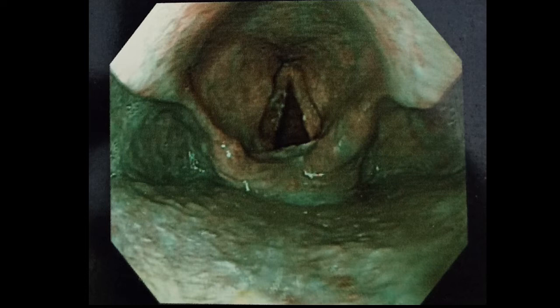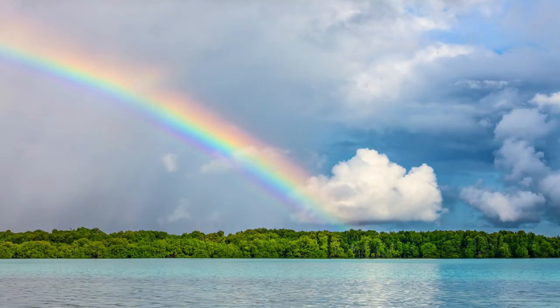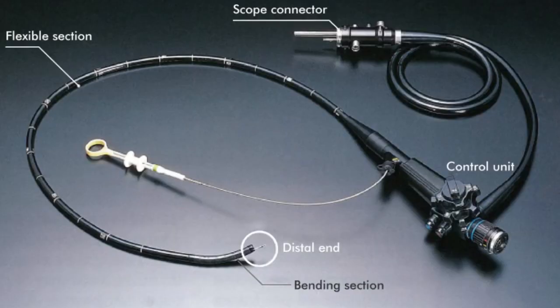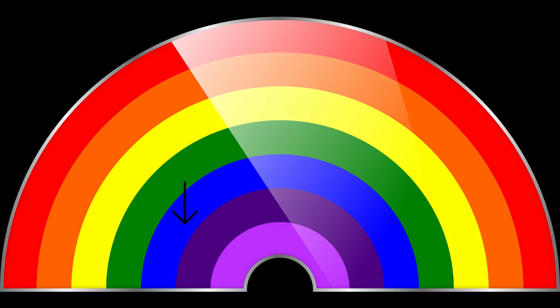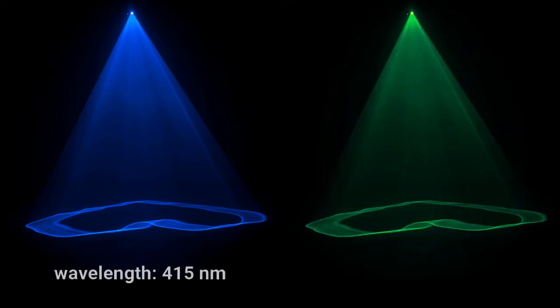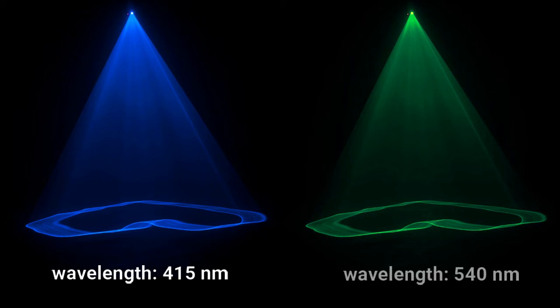Normal light has seven colors in it. In narrow band imaging, with the help of a switch in the endoscope, a special filter is electronically activated. This filter filters out all colors except the blue and green light from the normal white light, and only blue and green light are projected. Blue light has a wavelength of 415 nanometers and green light has a wavelength of 540 nanometers.